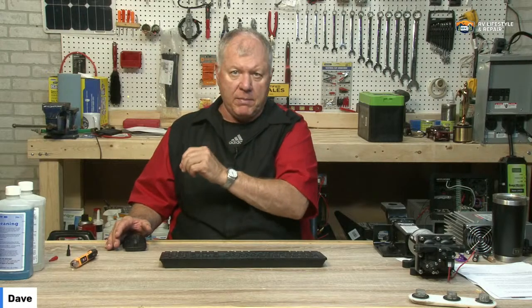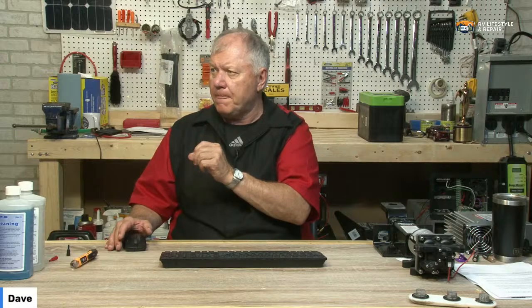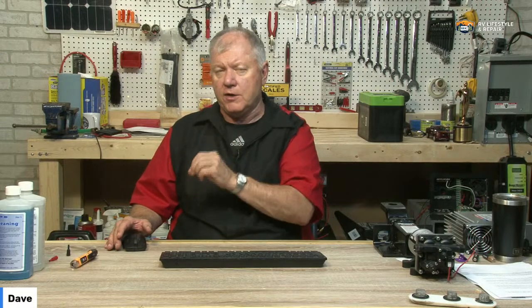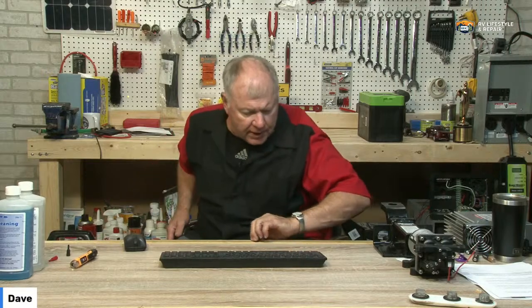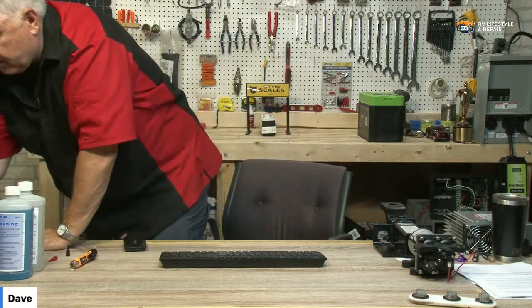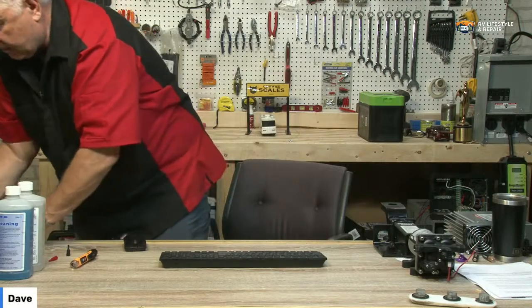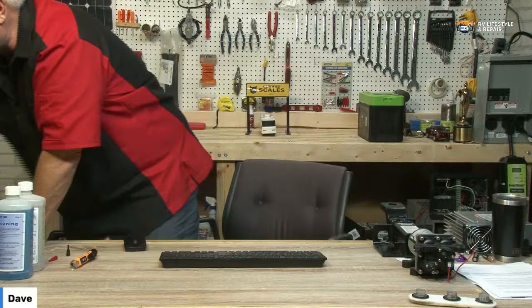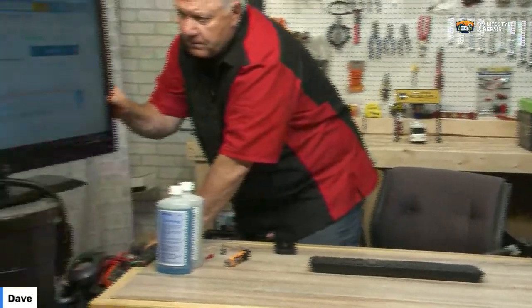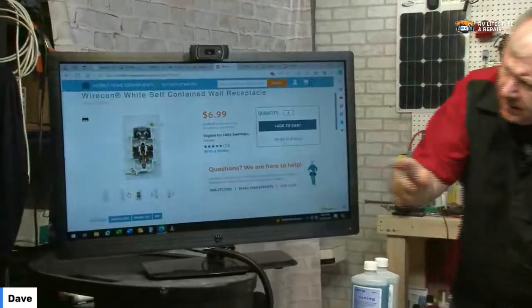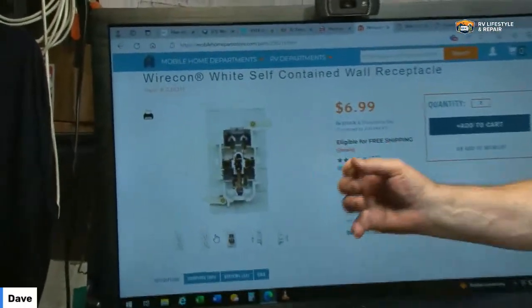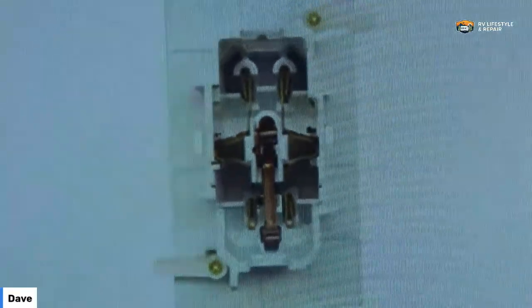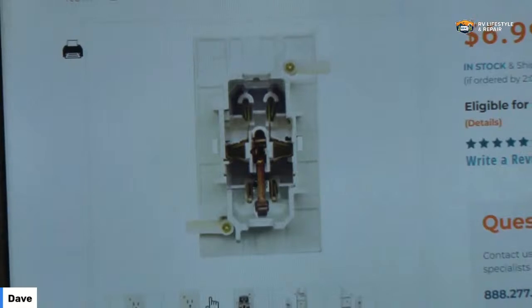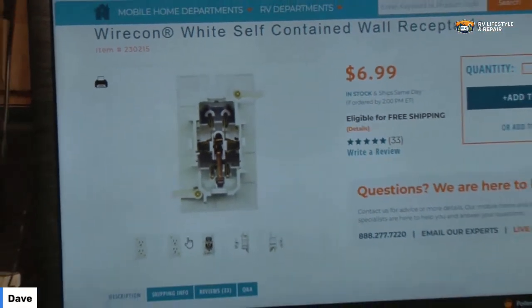Now what I don't like about this type of system is that it's too easy for these wires to slip out. I'm going to turn this around - we've got a couple minutes here so you can see this, and I've had this come up quite a few times with coaches. You can see right here, instead of traditional screws on the side, it has little spades, and the wire is supposed to just slip into it. So the tool he's looking for is some type of punch down tool that would punch that wire into that spade. I do not like those type of receptacles.